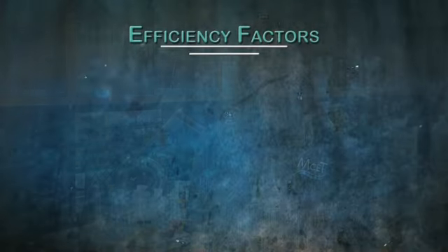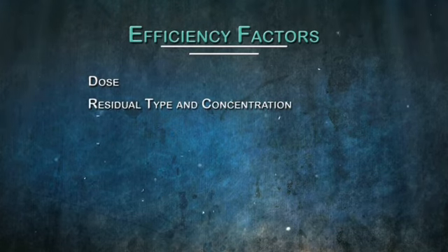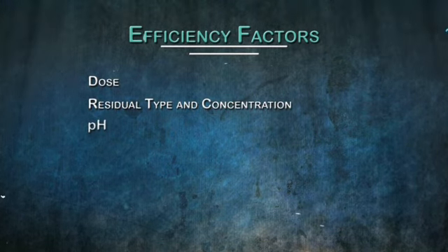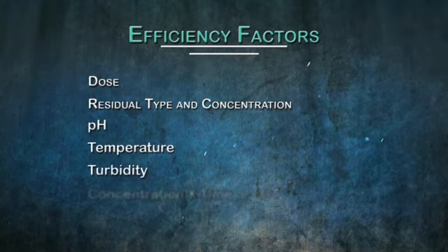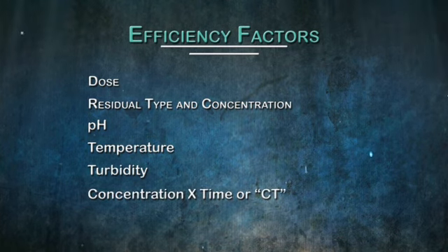There are several factors that affect the efficiency of disinfection. These factors include the dose, residual type and concentration, pH, temperature, turbidity, and concentration X time, or CT. In general, the highest levels of pathogen inactivation are achieved with high chlorine residuals, long contact times, high water temperature and good mixing, low pH, low turbidity, and the absence of interfering substances.